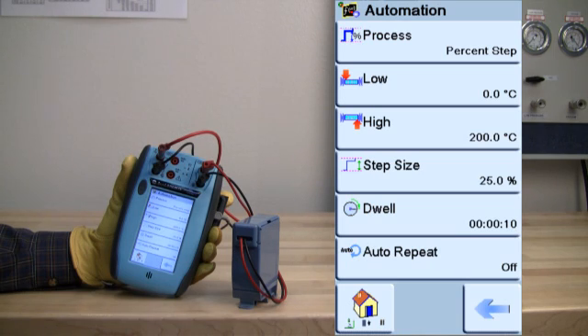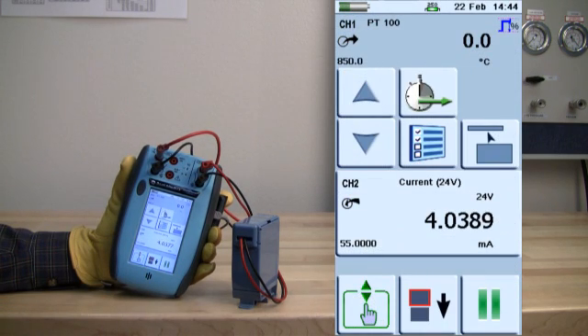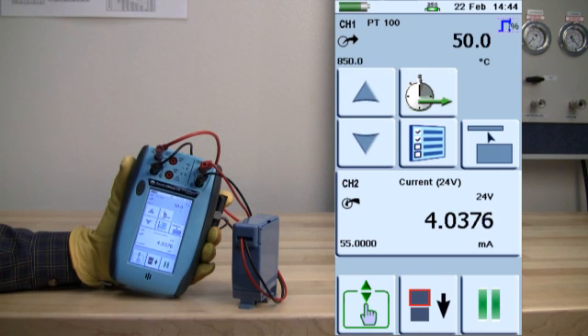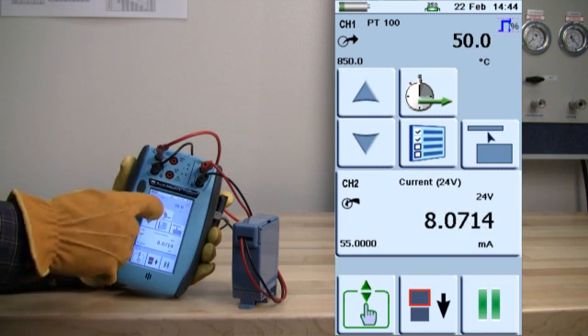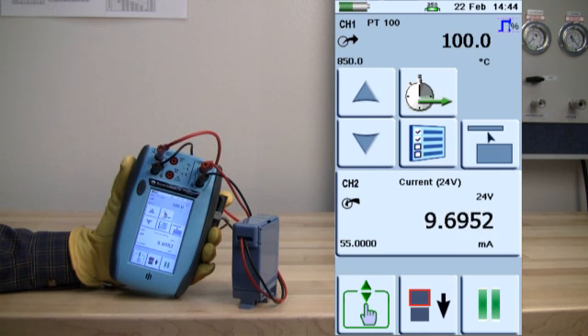In this demonstration, we have configured the DPI620 to perform a ramp test of an RTD. We have set the ramp at 25% increments, which for this device represents 50 degrees centigrade. For this test, channel 1 is configured to output a temperature signal, and channel 2 is configured to display the milliamp output signal from the RTD.